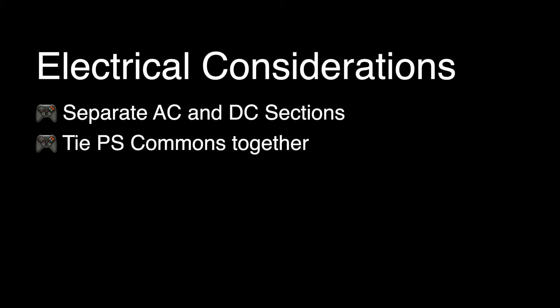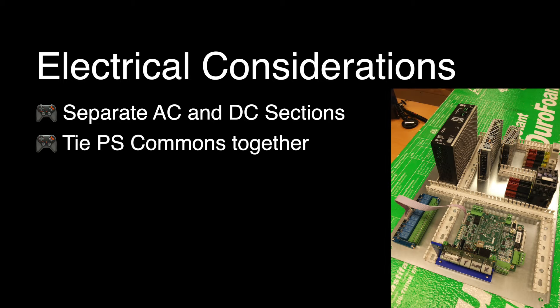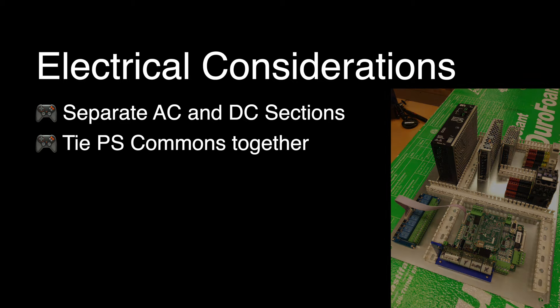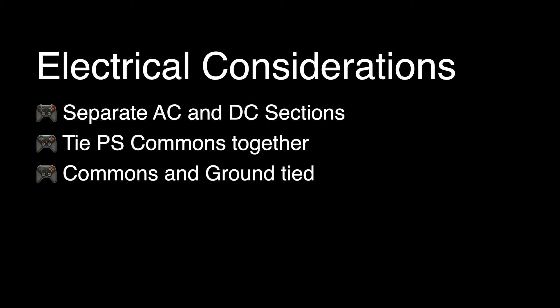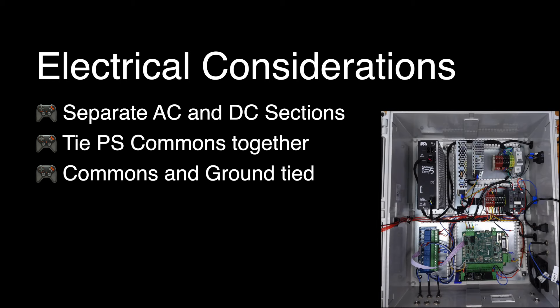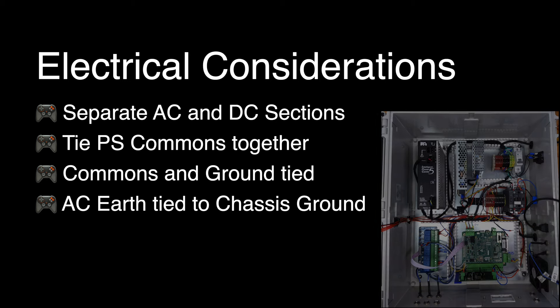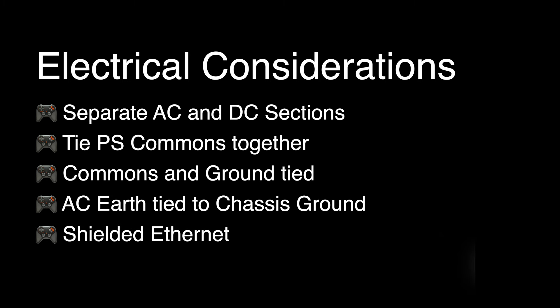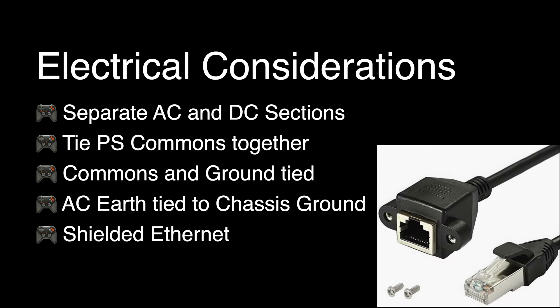The commons from all power supplies must be tied together to prevent floating grounds. The commons and chassis ground must be tied together. The AC earth is also tied to the chassis ground. Shielded ethernet must be used to communicate to the operator console.